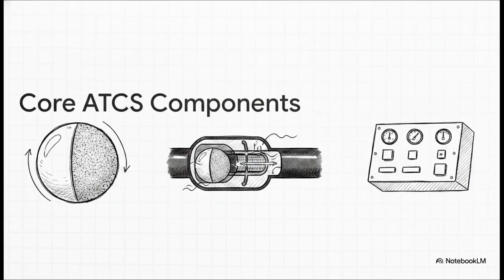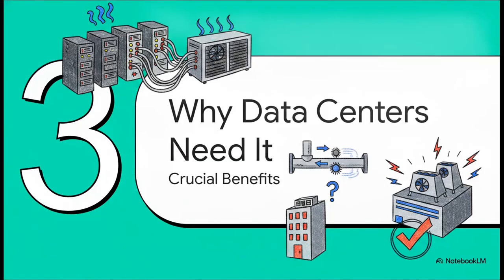The real genius, though, is in the hardware itself. First, you have these specialized sponge balls. We're not talking about your average kitchen sponge here. They're engineered from specific rubber or polyurethane materials to clean without scratching the tubes. If a facility has exceptionally tough scale, they can even coat these balls with a highly abrasive material called Carborundum. Next, there's the hydrodynamic strainer. This is absolutely crucial because it has to perfectly catch every single ball, but do it without blocking the massive flow of cooling water. And rounding out the whole shebang is the collector and control panel where the magic gets timed and programmed. Why data centers need it.